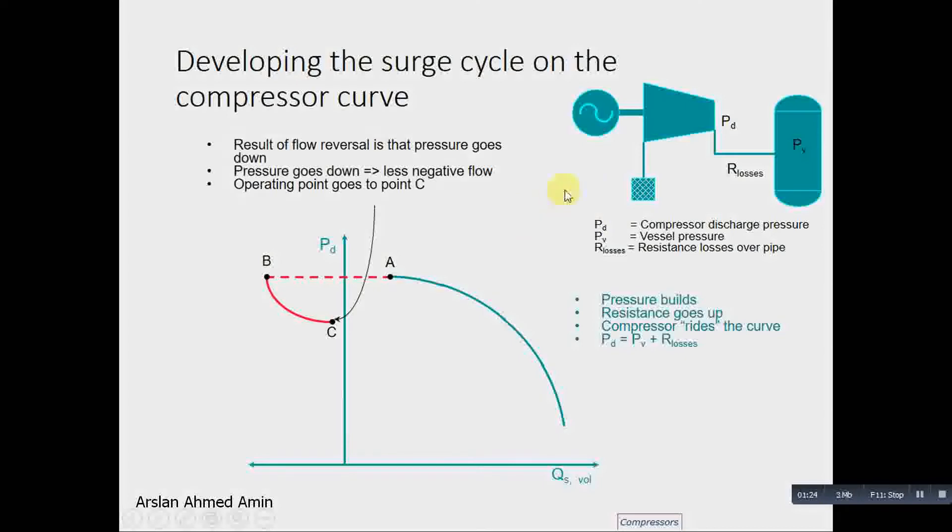But this is a momentary condition. The result of flow reversal is that pressure goes down with negative flow, and the operating point goes to point C. In the surge cycle, we see that the flow starts and the flow of the gas is between positive and negative.